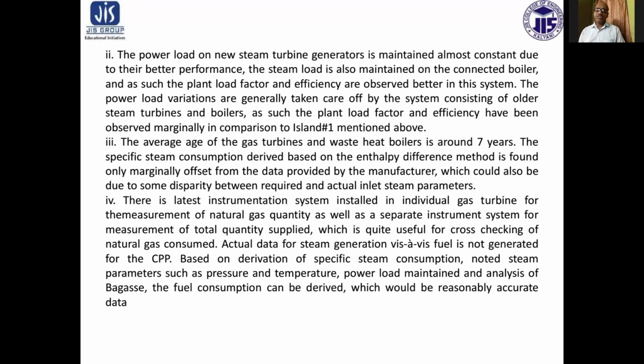The specific steam consumption derived based on enthalpy difference method is found only marginally offset from the data provided by the manufacturer, which could also be due to some disparity between required and actual inlet steam parameters.